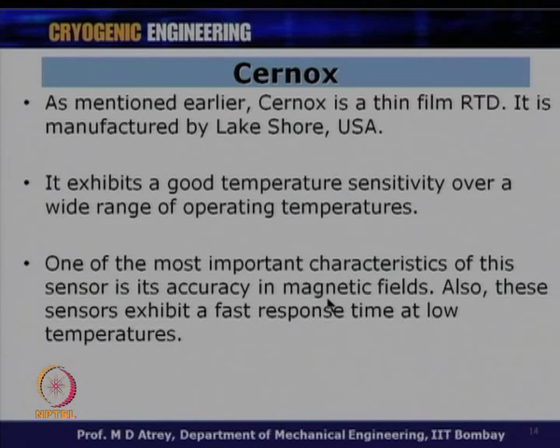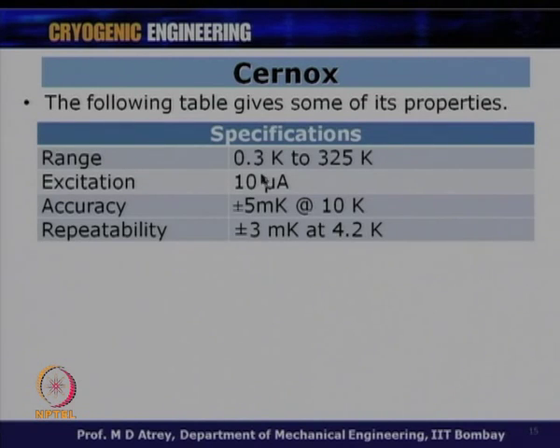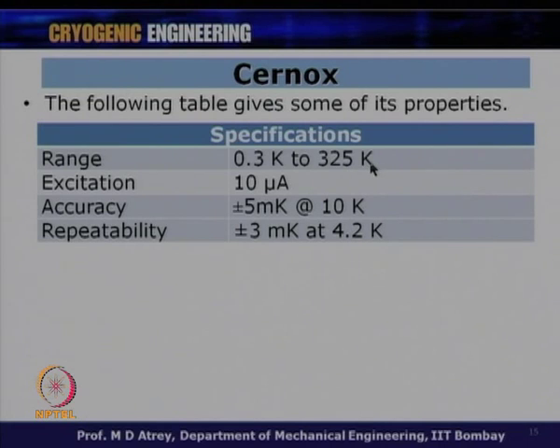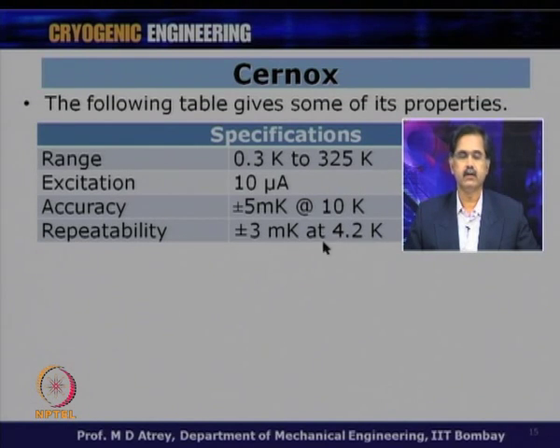Cernox sensors are packaged in a robust hermetically sealed casing similar to silicon diodes. The operating range is 0.3 Kelvin to 325 Kelvin — lower than silicon diodes' 1.4 K lower limit. Excitation is also 10 microamps. Accuracy is ±5 milli-Kelvin at 10 K, and repeatability is ±3 milli-Kelvin at 4.2 K.